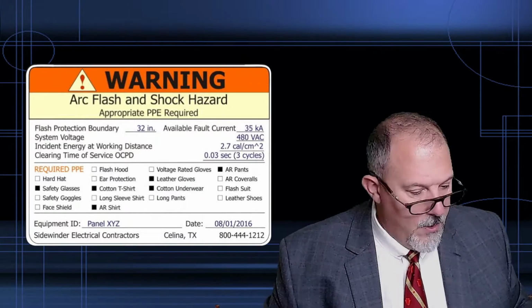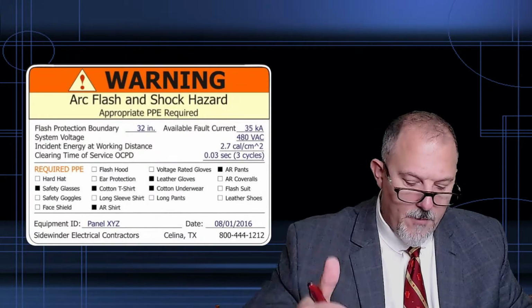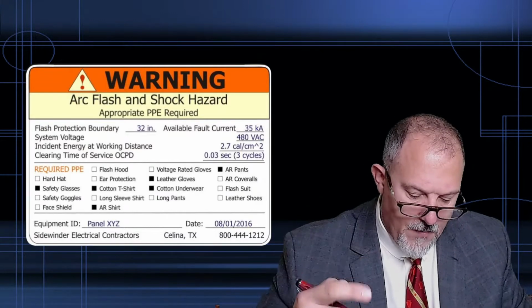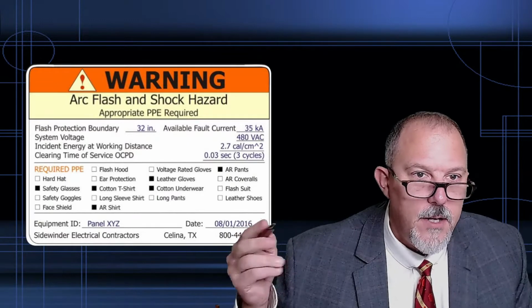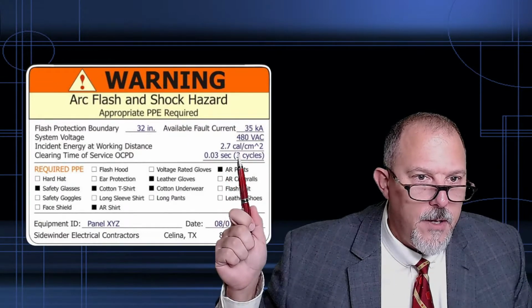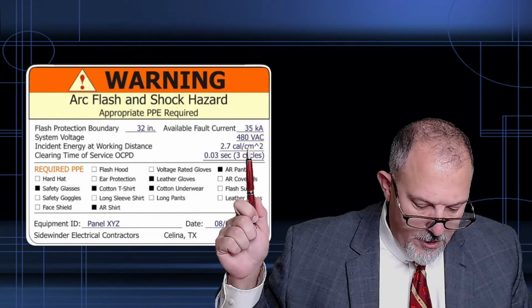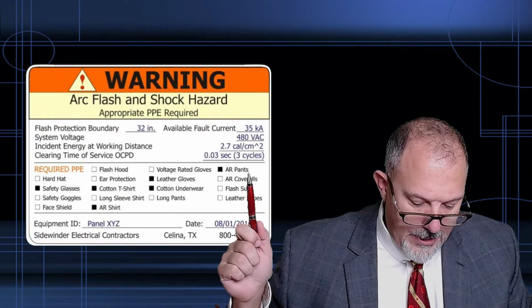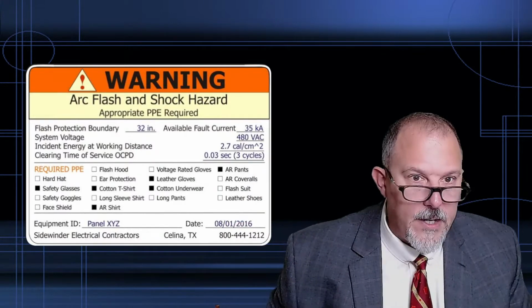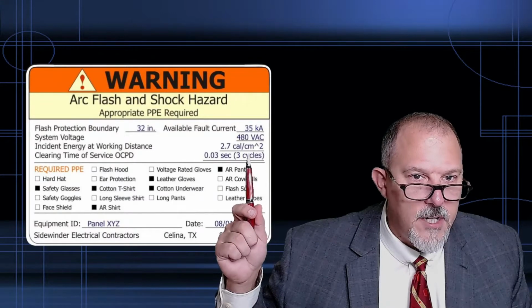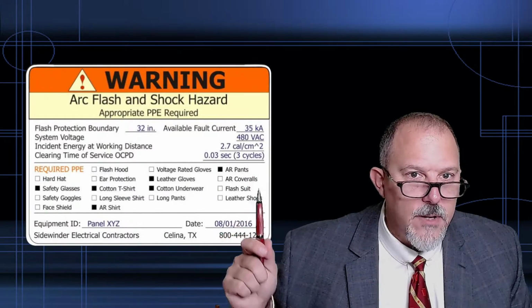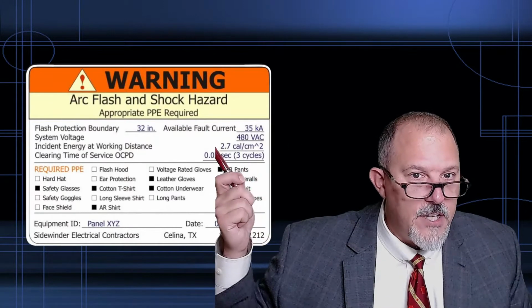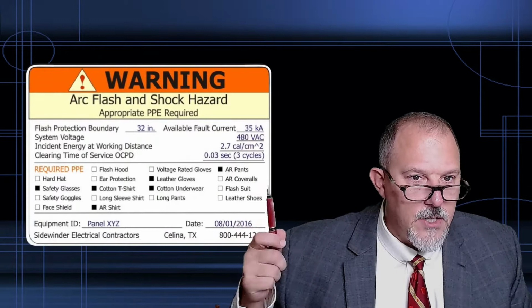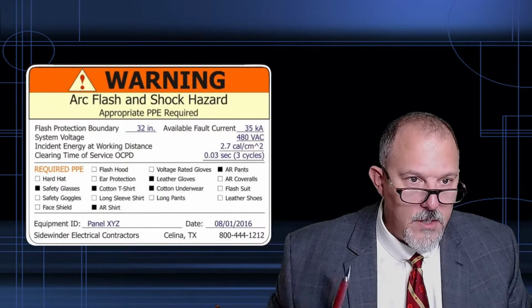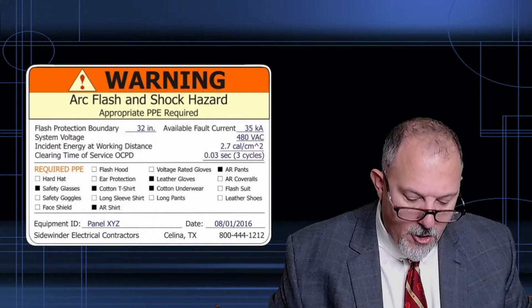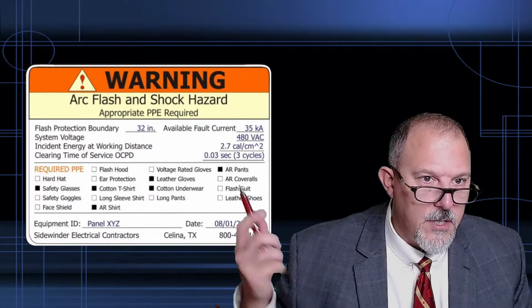All right, your equipment labeling, 130.5(H), says nominal system voltage, arc flash boundary, and at least one of the following: available incident energy and the corresponding working distance. You have your arc flash boundary, your incident energy, your nominal system voltage. So I have 2.7 calories per centimeter squared. Where's my working distance? I don't have a working distance. Oh, yes, that's the arc flash protection boundary. I'm missing a working distance on this label. That would not meet it. Or no, required PPE: minimum arc rating of clothing, site-specific level of PPE. So there's your required PPE.